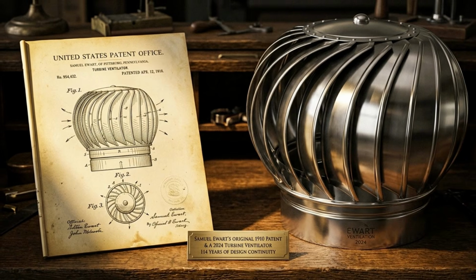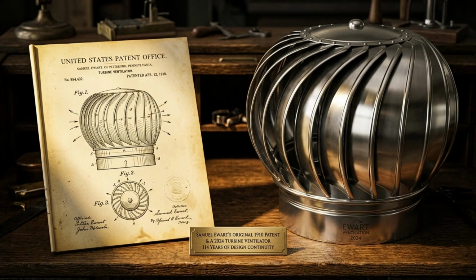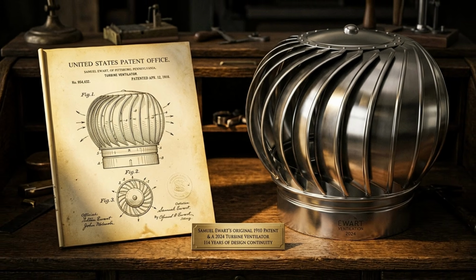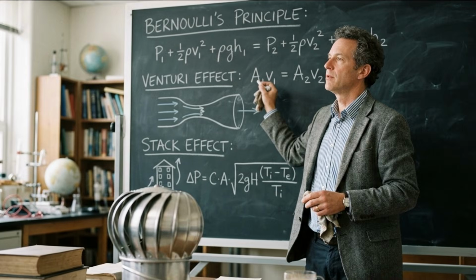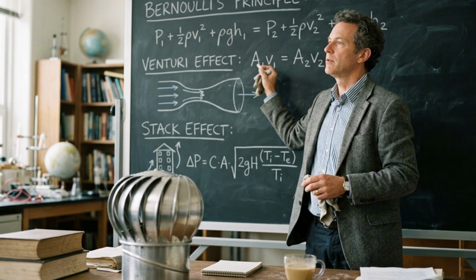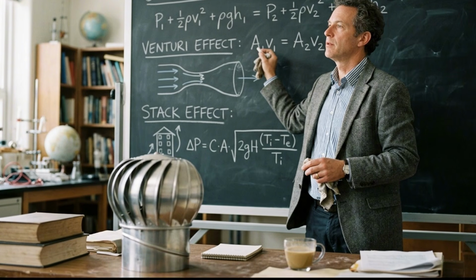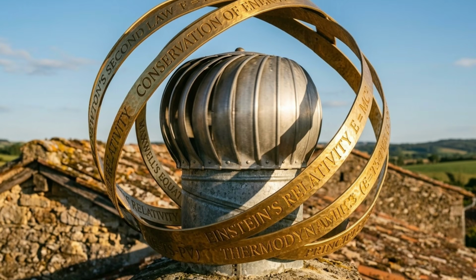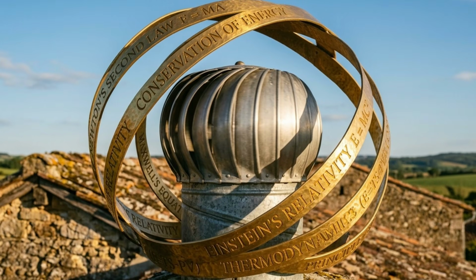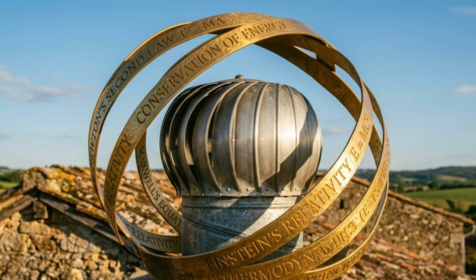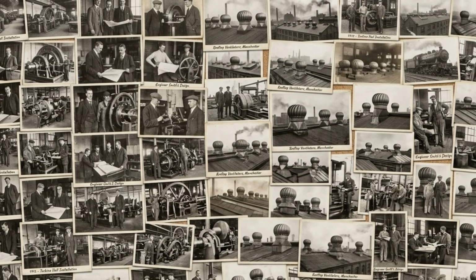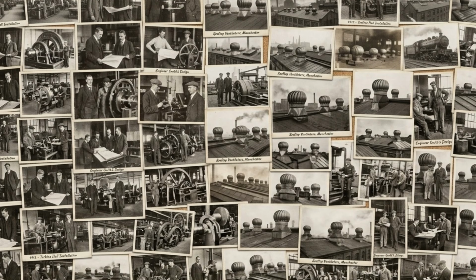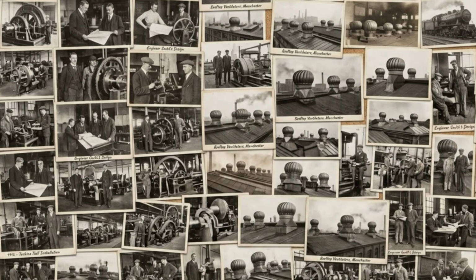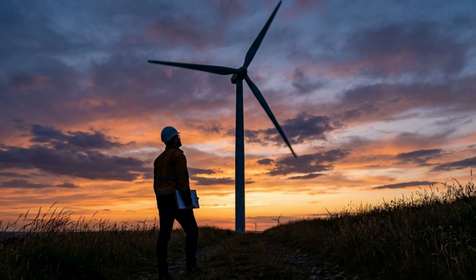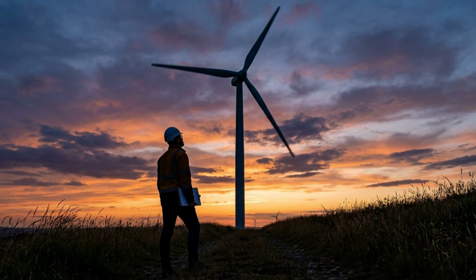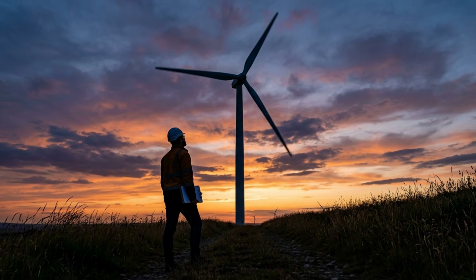In southern climates, the energy savings can pay back the entire installation cost in just 3 to 5 years. It is a very smart investment if you aren't overly concerned about noise or suburban aesthetics. But in cold climates, the turbine can bring more unnecessary trouble than actual cooling benefits. During winter, internal moisture from the home can freeze directly onto the turbine's metal vanes. This ice layer can jam the system completely at the very moment when ventilation is needed most.